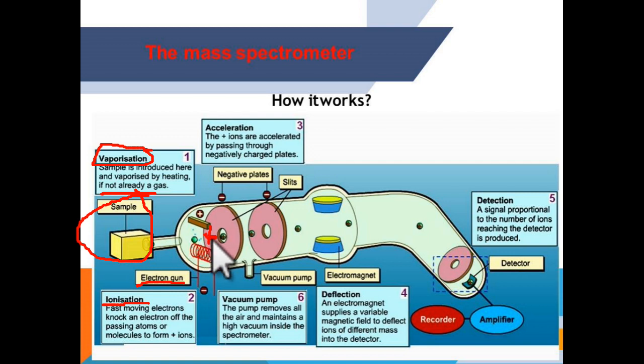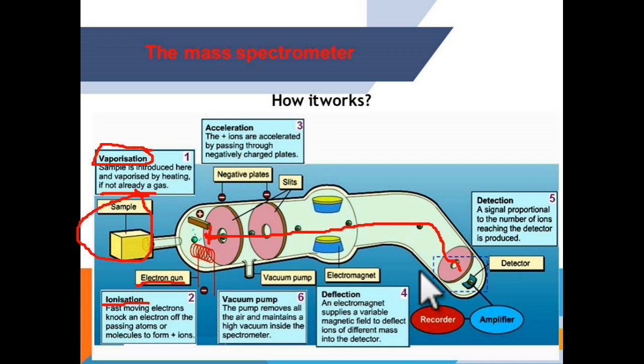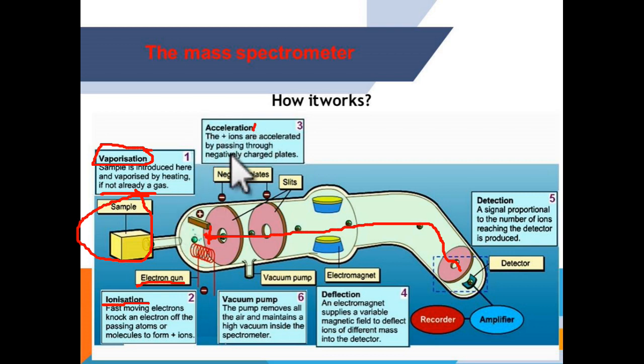After bombardment the atom becomes an ion, and we need to force the ion to move through the tube until it reaches the detector. This is done in the acceleration chamber. The ion is accelerated by passing through a negatively charged plate, which forces it to move faster through the instrument.